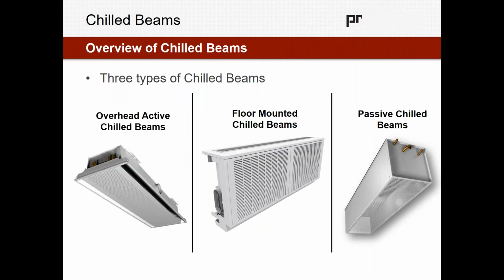There are really three types of chilled beams. The one that I see most commonly utilized, and the one intended for this discussion and application, is that overhead active chilled beam. It would be the most popular one, although we do see it in floor mounted configurations, which we can see in the center of the screen. It's the same components, just reconfigured in more of a wall mounted fan coil style configuration. And then on the right hand side, we see that passive chilled beam, which has no airflow supplied directly to it. It's just entraining and mixing air in the space without the utilization of any primary air.